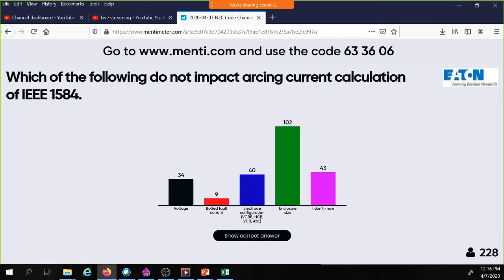We know voltage does. If I have a 480 volt system, think of voltage as pressure in water, right? If I have a lot of pressure pushing my current through the system, a higher voltage, I'm going to get higher arcing currents. I'm going to get more energy. Bolted fault current values matter because I calculate arcing currents based upon the bolted fault current. If I have so low of a bolted fault current, the arc doesn't even sustain itself. It self-extinguishes. I could have a very high bolted fault current value, which will generate very high arcing currents. We're going to talk about that.